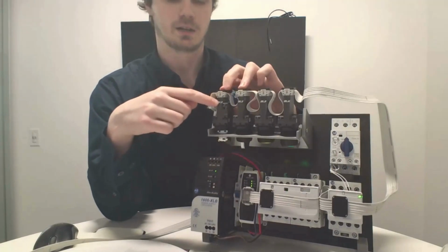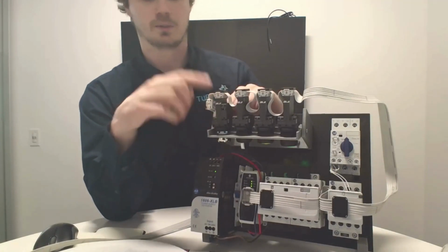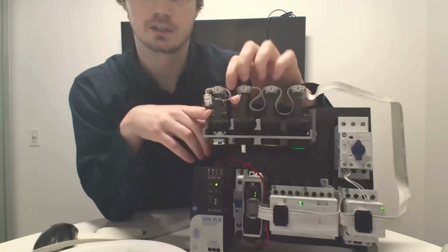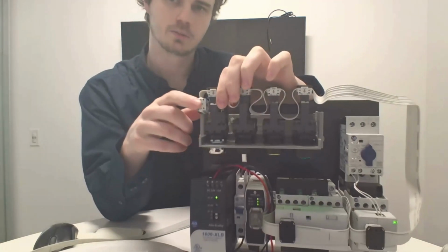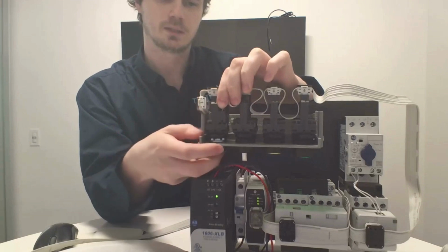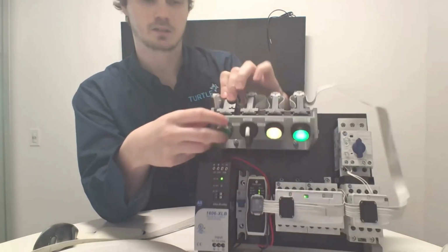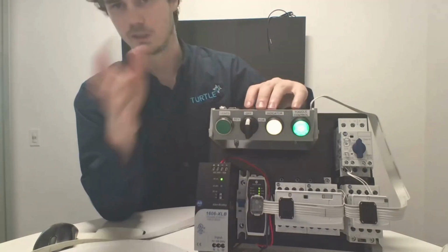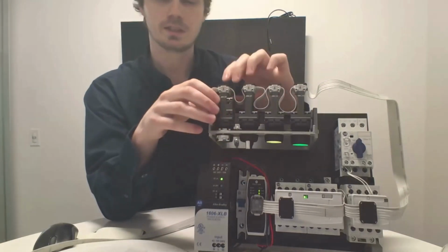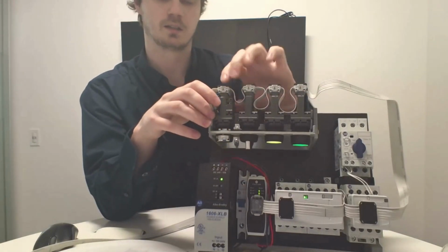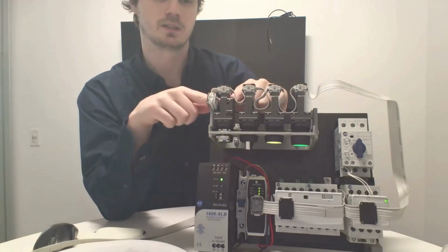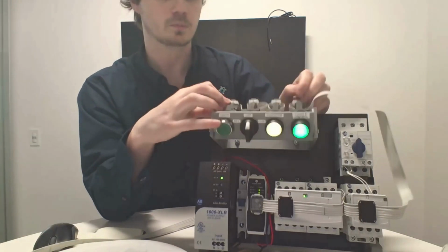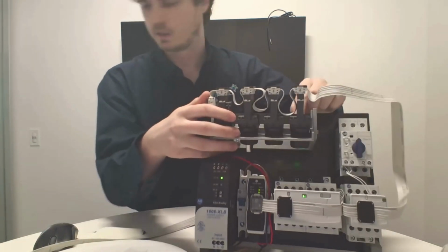And this is going to be how you get your buttons to work, your 800F buttons. As you can see, I have a standard contact shoved onto one of these buttons. So if I wanted standard contacts to go with the Ethernet IP and cabinet solution, that's perfectly fine. It doesn't work with safety ones yet, as they're a little bit too tall to squeeze in next to this, but you can put on, once again, 2 different contacts per button. They pop on and off.